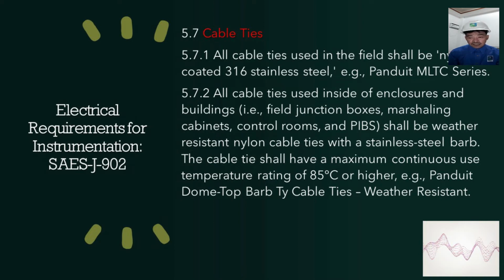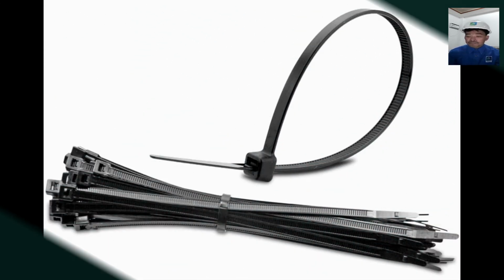And we have the example brand, the Panduit MLTC series. All cable ties used inside of enclosures and buildings, like the field junction boxes, marshalling cabinets, control rooms, and process interface buildings, shall be weather resistant nylon cable ties with a stainless steel barb. The cable tie shall have a maximum continuous use temperature rating of 85 degrees C or higher.